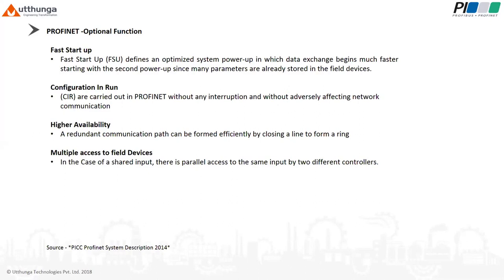In the case of shared input, there is parallel access to the same input by two different controllers. Thus, an input signal that must be processed in two different controllers of a system does not have to be wired twice or transferred via CPU to CPU communication.